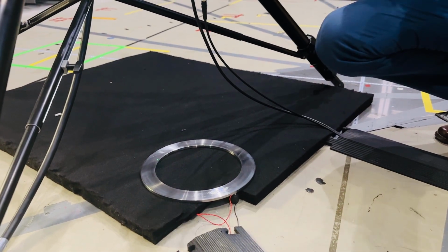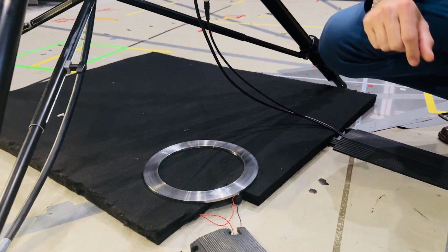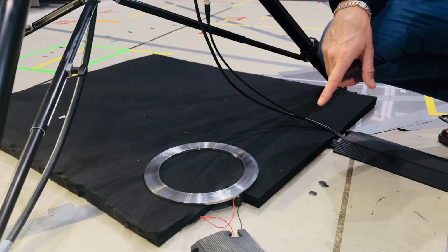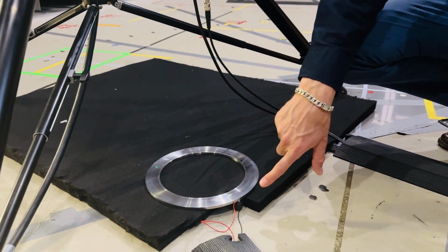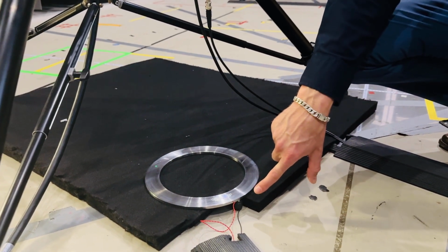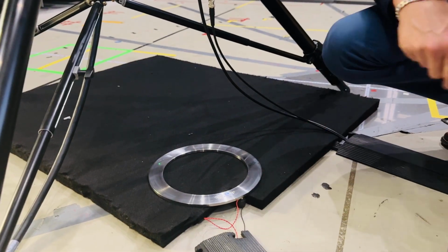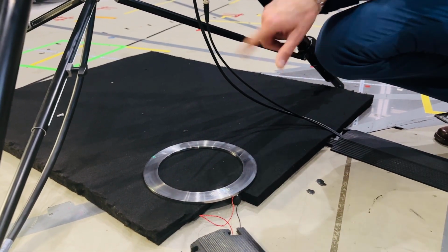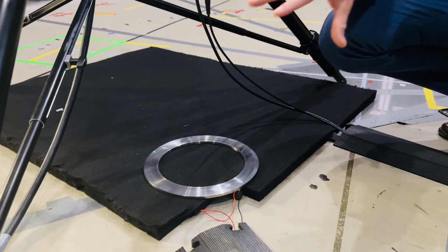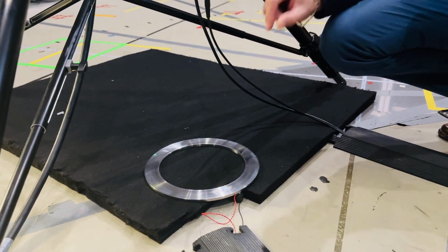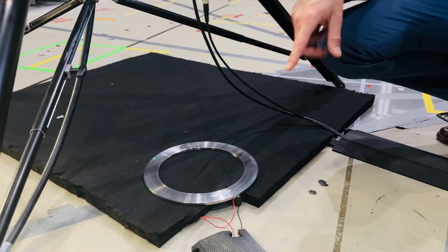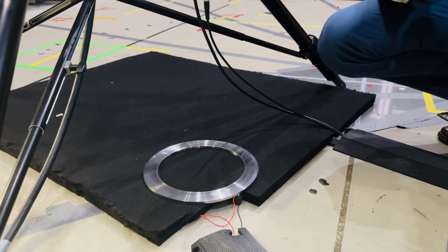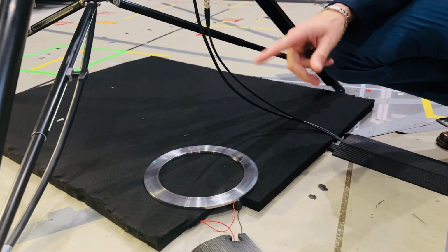And the combination of these two non-contact vibration measurement techniques with the laser vibrometer and essentially very light mass loadings, almost zero mass loading from the mini-inertial shaker, and zero stiffness loading to the disc means that we're able to very precisely characterize the vibration behavior of these kinds of structures. I'm talking about resonant frequencies and mode shapes.